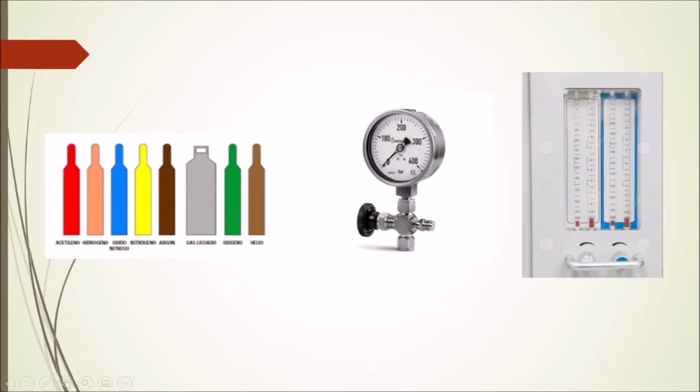The patient breathes a mixture of oxygen, the vapor of a volatile liquid, nitrous oxide, and other halogenated hydrocarbon anesthetic gases. They are usually extracted from the central gas supplies of the hospital. It is called fresh gas, and the pressure is approximately 45 pounds per square inch (psi).